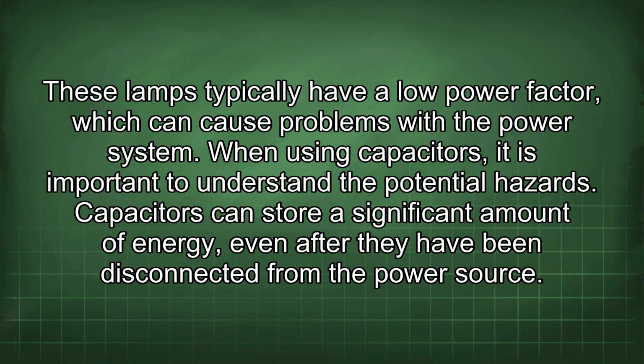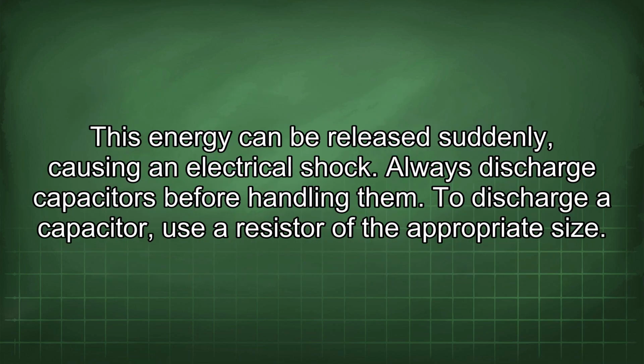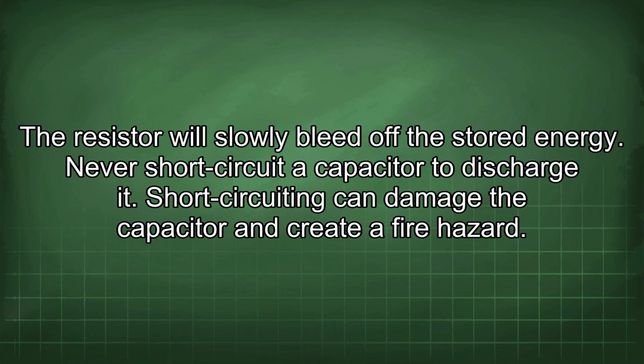When using capacitors, it is important to understand the potential hazards. Capacitors can store a significant amount of energy even after they have been disconnected from the power source. This energy can be released suddenly, causing an electrical shock. Always discharge capacitors before handling them. To discharge a capacitor, use a resistor of the appropriate size. The resistor will slowly bleed off the stored energy. Never short-circuit a capacitor to discharge it. Short-circuiting can damage the capacitor and create a fire hazard.